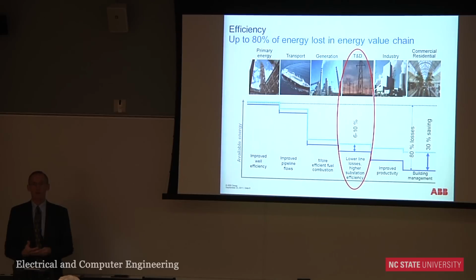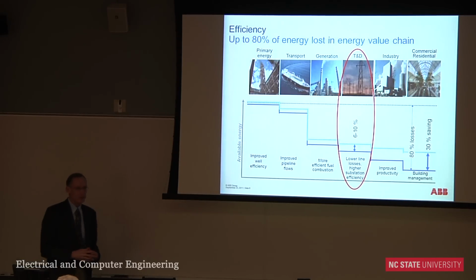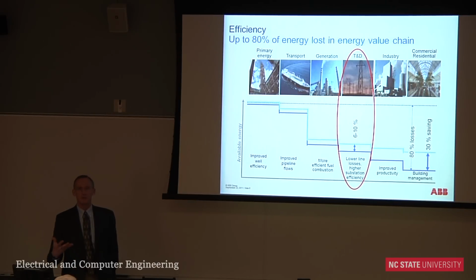Volt-var control and conservation voltage reduction are strategies utilities are implementing today to lower those losses, typically saving in the range of 4 to 5%, which frees up capacity in the grid and also reduces generation requirements.